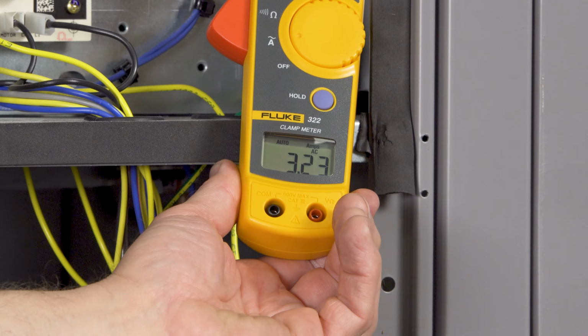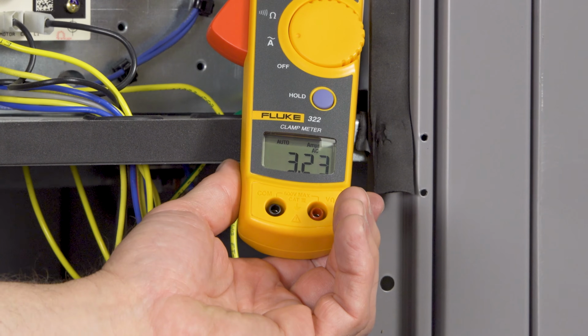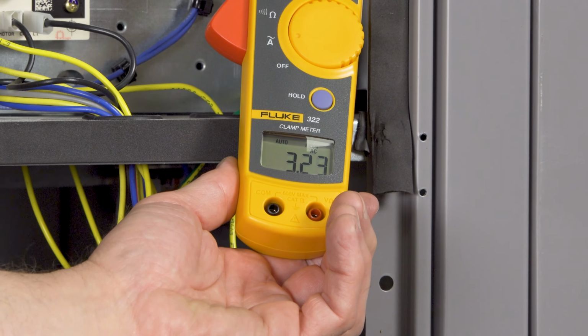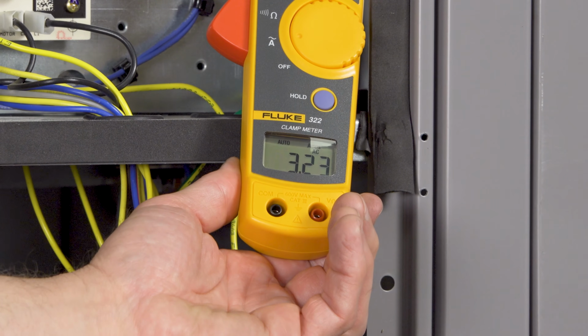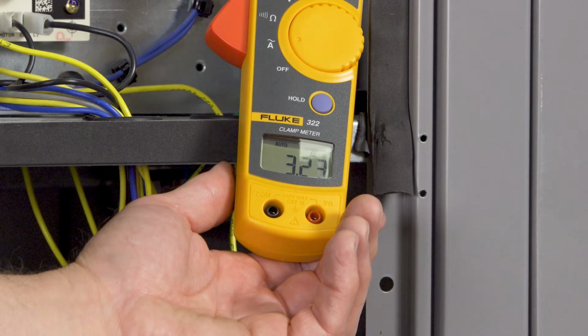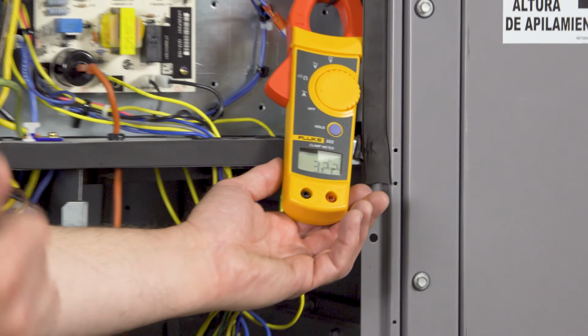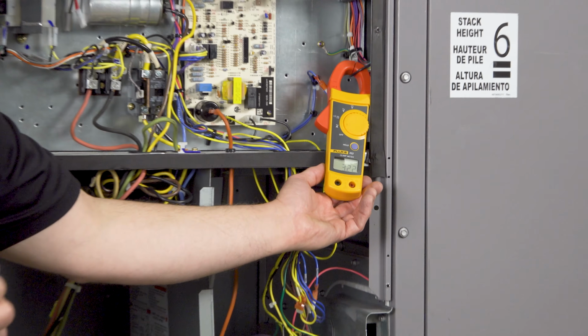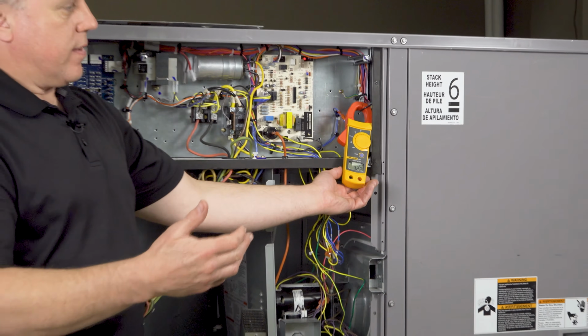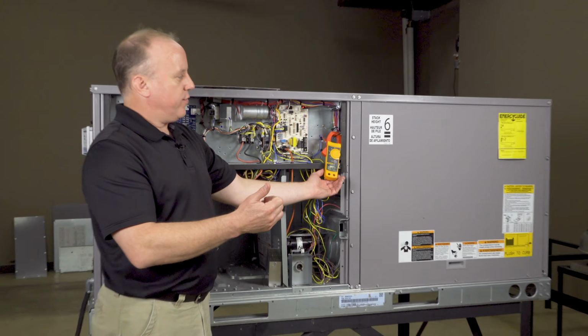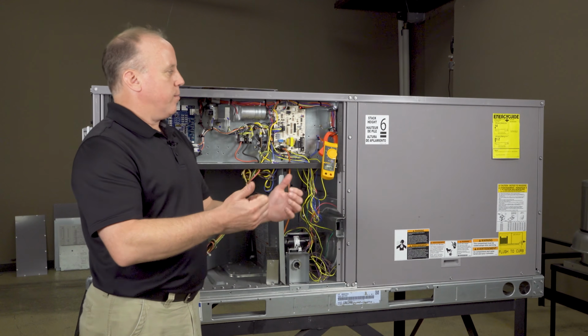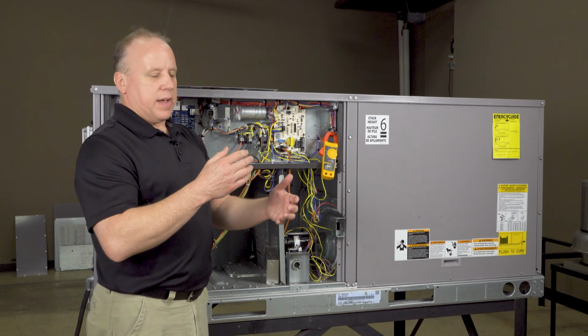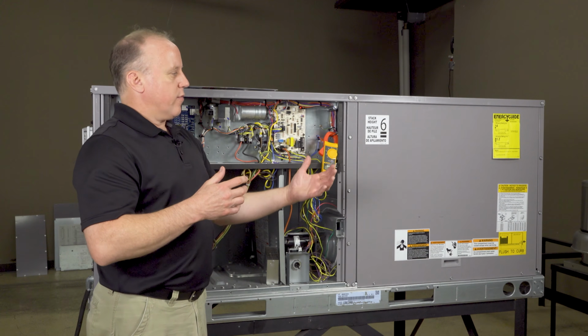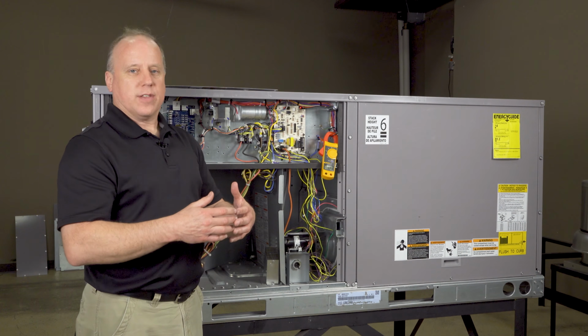And we are running about 3.2 amps on our blower motor for the unit. So this is going to give us an idea of what's going on. If amps, again, are running high, we know there's a problem with possibly the motor itself. Say on the indoor blower motor, if the amp draws real high, is it because of our static pressure? Do we have restrictions somewhere? Are we not getting air to the unit?